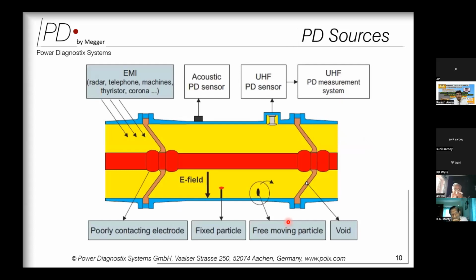If we understand, there are a few reasons why partial discharge occurs in a GIS, and the obvious reasons are certain defects. One of them is a void, which is a permanent failure or a permanent issue in the hard structures. It could be a free moving particle inside the GIS which is left unattended during commissioning, or which would have entered during evacuation and filling of SF6 gas. A fixed particle or a protrusion on the surface of the GIS, or a poor contact electrode which could have not been aligned properly or would have misaligned due to vibrations because of breaker operations. So these are the few reasons because of which the partial discharge phenomenon starts inside the GIS.